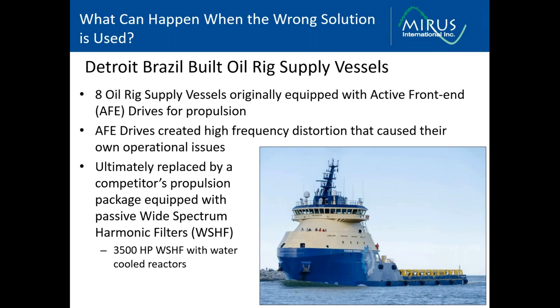The high-frequency noise injected by the switching of the IGBTs in the AFE drives was causing their own equipment to fail. Ultimately, the entire propulsion electrical package had to be removed and replaced by another manufacturer's system equipped with a wide spectrum harmonic filter. This was a very costly problem for them, with the strip out being over $2 million cost.